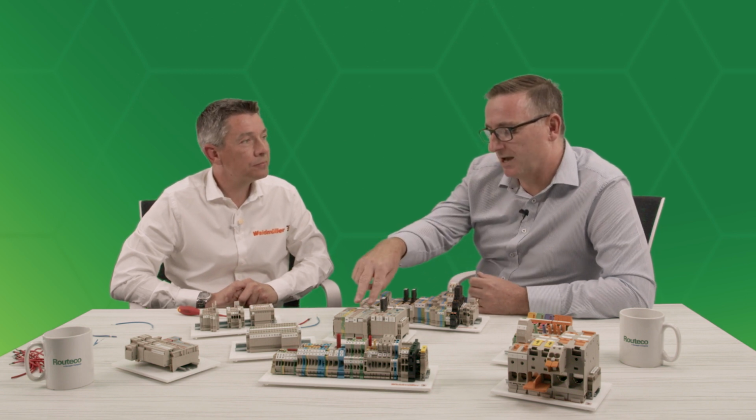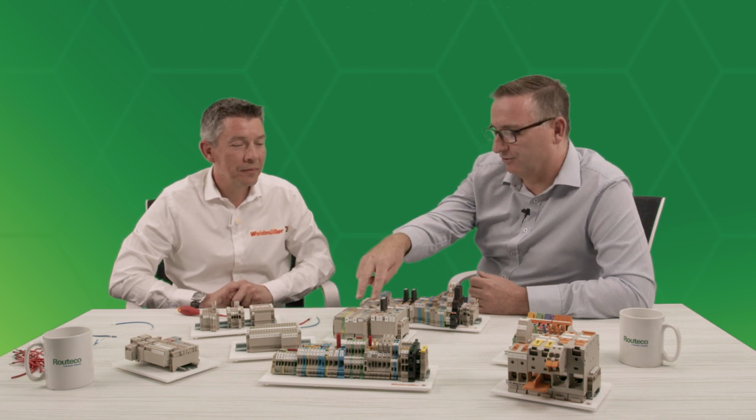Part of the conversation today was looking at the distribution products that you offer, because I think these have gone under the radar a bit with customers, though I can see the benefits. Tell us more about these and the advantages for customers, especially those with really tight panel space. Certainly. When we introduced the A-Series, we looked at how terminals were used. You can take a standard 2.5mm feed through terminal and use it for all sorts of things. But to distribute power, doing a large row of terminals for your 24 volts and another large row for 0 volts is very panel and space intensive.